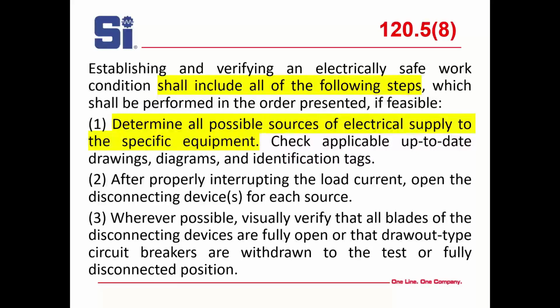That could be something that you believe is de-energized and is still energized. So you have to check applicable, up-to-date drawings, diagrams, and identification tags. And you have to be careful. This is a big problem. After properly interrupting the load current, open the disconnecting device for each source. Wherever possible, visually verify that all blades of any disconnecting device are fully open, or that the draw-out circuit breakers are withdrawn to the test position or fully. And again, we're talking primarily medium voltage here.